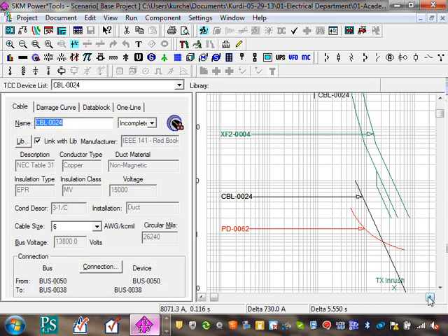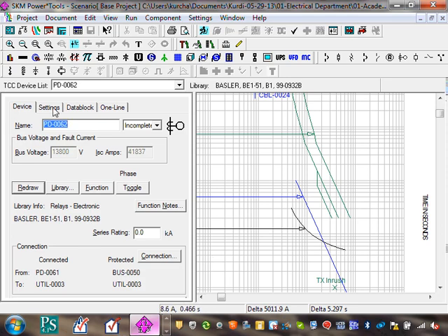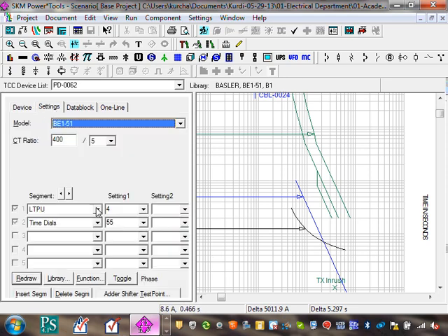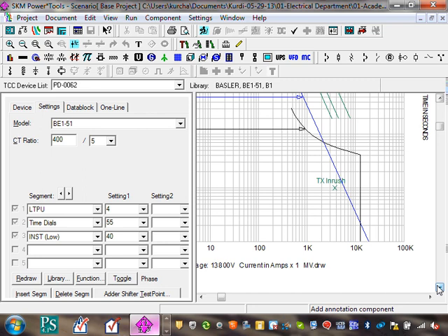6. So if I set my relay the way I'm setting it right now, and even if I put an instantaneous in it, let's go put an instantaneous low. I put my instantaneous. Can you guys see my instantaneous jumped in it? I want you to pay attention to this. Here's what my relay is going to pick.